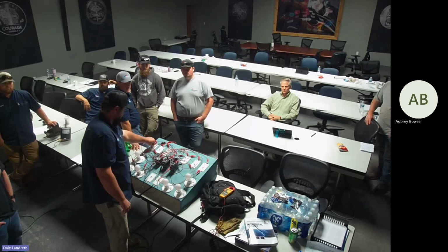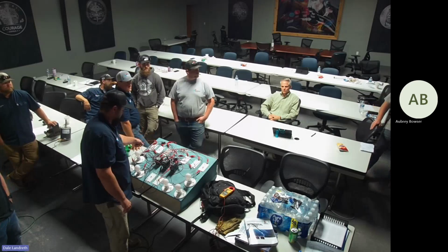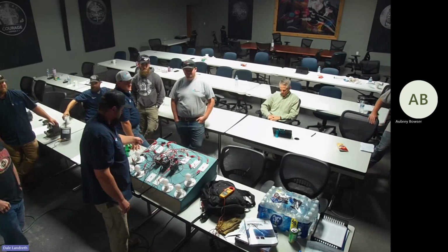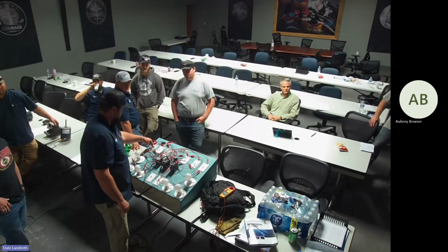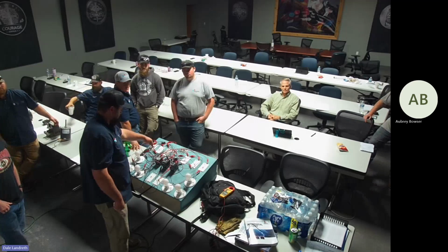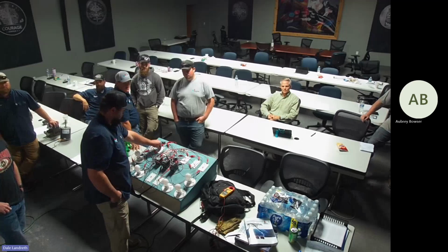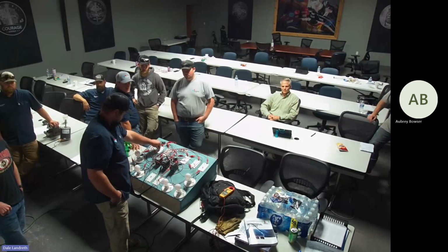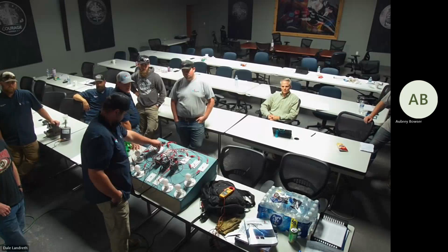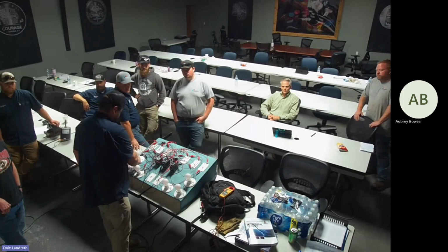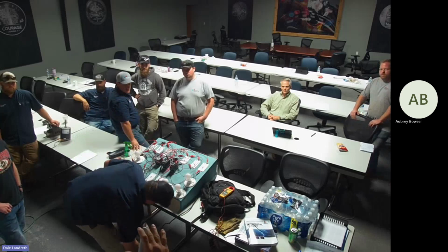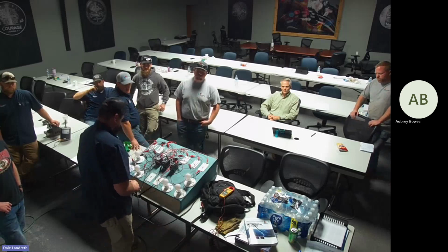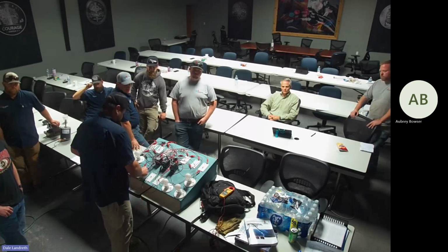Load build up, we just did the answer. So if I were to shut a compressor off and immediately try to start it, what's my refrigerant pressures at? Already loaded up. My suction pressure is what - lower. My discharge pressure is what? So that means my compressor is trying to start at a differential pressure, which means it's going to take more starting torque to overcome that differential pressure.